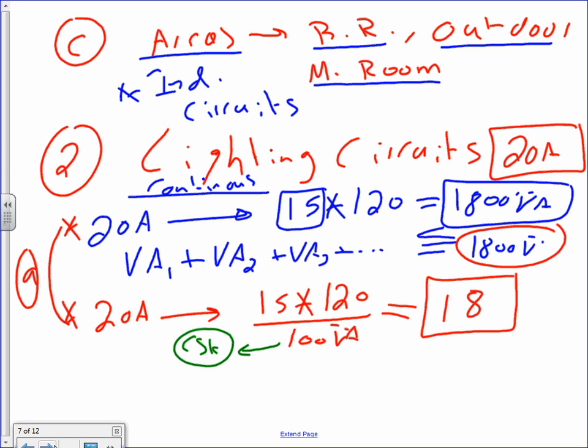So if you use VFDs later on, you say, Chad, I was able to put 30 of them on one circuit because I added the volt amp of all my VFDs and they don't exceed this number, so I can put 30 of them. Cool? So for the time being, for our design, what's our magic number for circuits? 18 of them. Can I have a thumbs up, Chad?